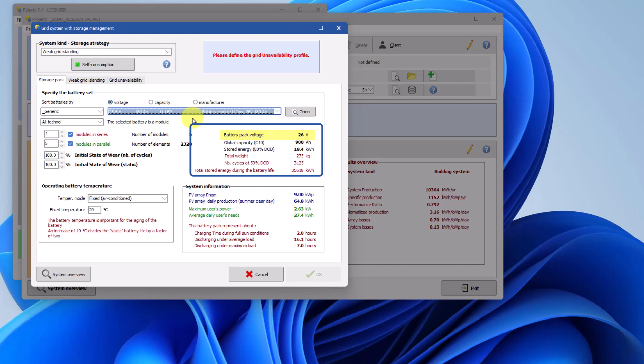The C10 rating represents the battery's capacity when fully discharged over a period of 10 hours. The stored energy at 80% depth of discharge (DOD) indicates the energy stored in a single battery cycle. It is important to note that for lithium-ion batteries, the charging cycle should never reach 100% DOD to avoid damaging the battery. The total weight of the battery pack is also displayed, giving you an idea of the physical size. The next line shows the number of cycles that can be performed at 50% DOD before the battery reaches the end of its life.